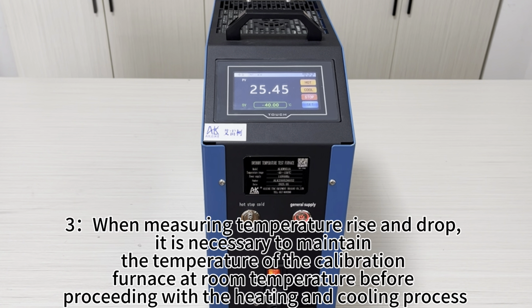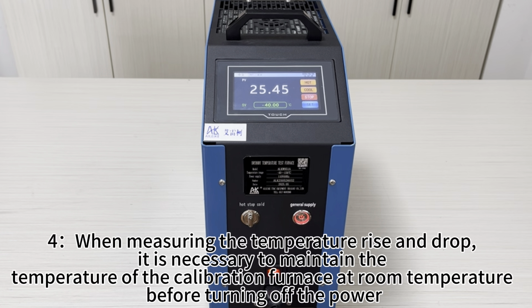Third, when measuring temperature rise and drop, it is necessary to maintain the temperature of the calibration furnace at room temperature before proceeding with the heating and cooling process. Fourth, when measuring the temperature rise and drop, it is necessary to maintain the temperature of the calibration furnace at room temperature before turning off the power.